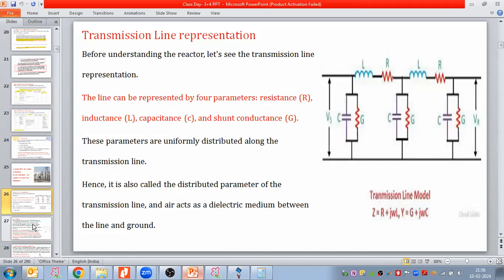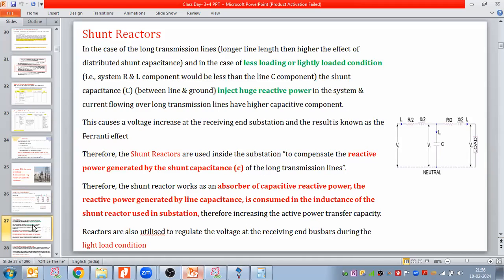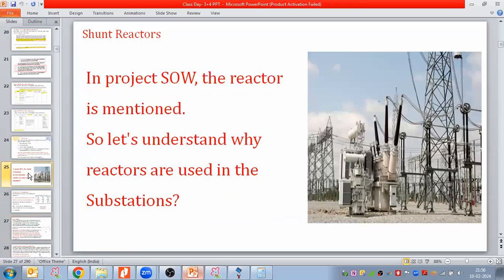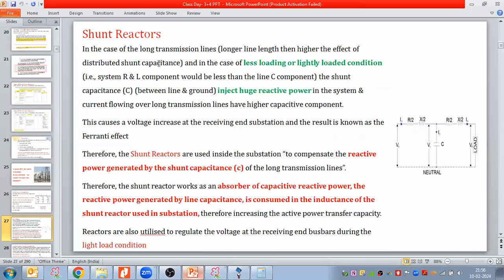Now, whenever we have a longer transmission line, it becomes important. In a short transmission line, the reactor will not come into use. So whenever we have longer line length, higher is the effect of the distributed shunt capacitance. And in the case of less loading, a lightly loaded condition, when your loading is less, your resistance and inductance component would be less compared to the line capacitive component.